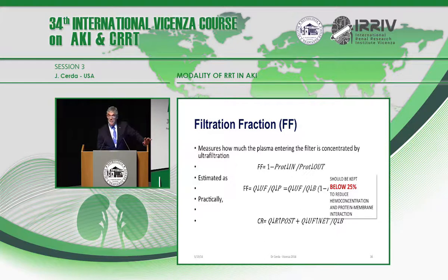The other issue to remember, though, is the magnitude of the ultrafiltration has an impact on the filtration fraction, which is a measure of how much the plasma entering the filter is concentrated by ultrafiltration. Necessarily, if you filter water, less water comes out of the filter than the water that enters the filter.